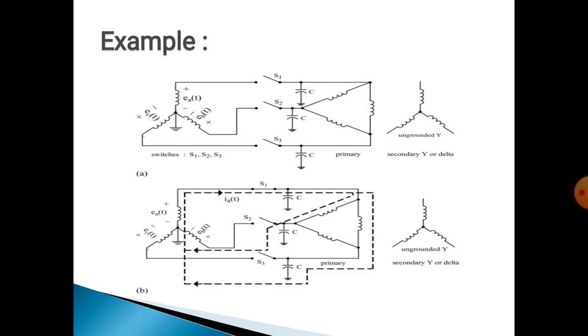And next, this is an example of ferroresonance condition. In this circuit, we have considered energizing and de-energizing of the primary of a transformer. The switch is connected to the primary through a length of cable, and the switching device may be mounted at the top of a pole with the transformer nearly at ground level.